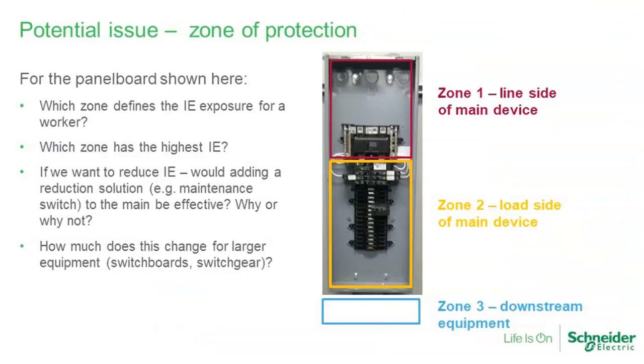But a potential issue that we need to consider when we look at these things is zones of protection. And I've got what's probably about the simplest thing here on the right, just a low voltage panel board. And I've got a couple of zones shown here. Zone 1, the line side of the main protective device, so maybe those main lugs right there at the top of the breaker. We don't have cables coming in on this one, just to simplify it a little bit. My energy is a little bit higher there than for Zone 2, the load side of the main device. Typically, that would be the case. Zone 1 would typically be higher because in a power system, we want coordination between breakers. That means that stuff that's further up toward the source takes a longer time to clear the fault. So Zone 1 is typically higher energy than Zone 2.